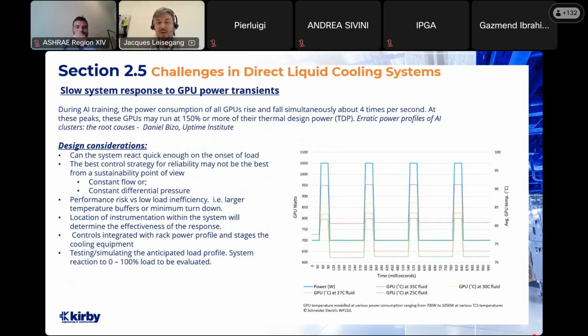Practically, the location of instrumentation within the system plays a big part in determining how effective the system is in responding to load and responding to higher temperatures. The control systems and control strategies that we have need to be more multidisciplinary. They need to be integrated with the rack power profile, and that stages the cooling equipment on ahead of time before servers start overheating. If we know when the load is coming up, we can start staging up the chillers and the cooling equipment ahead of time.